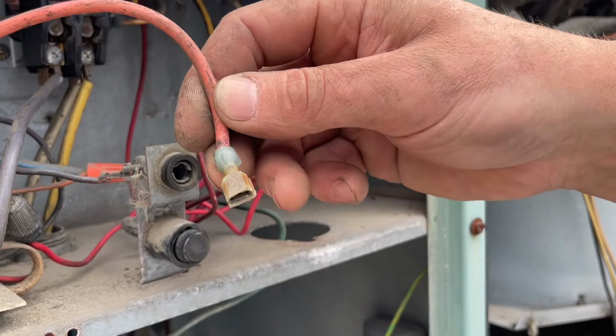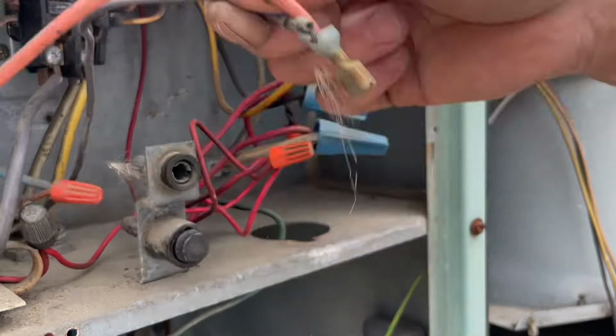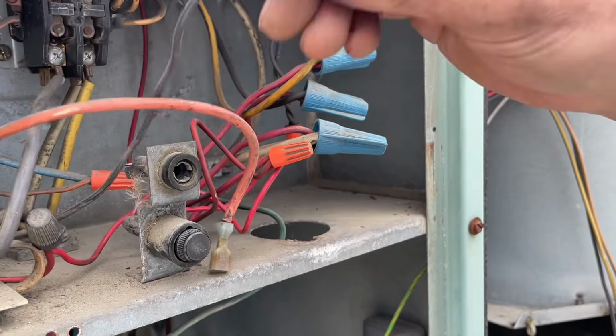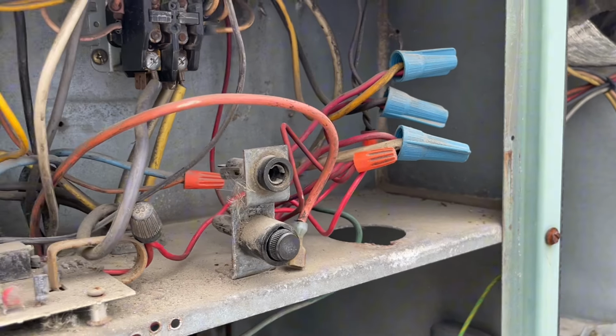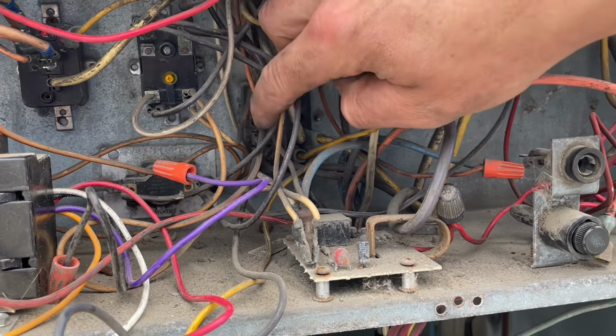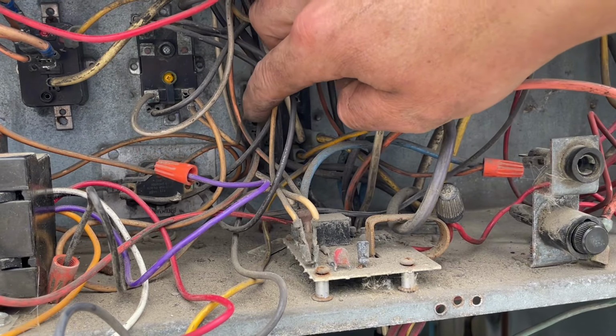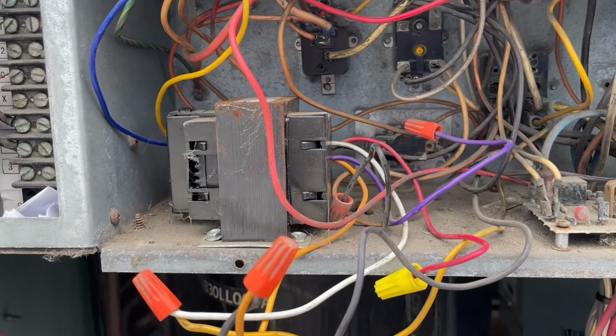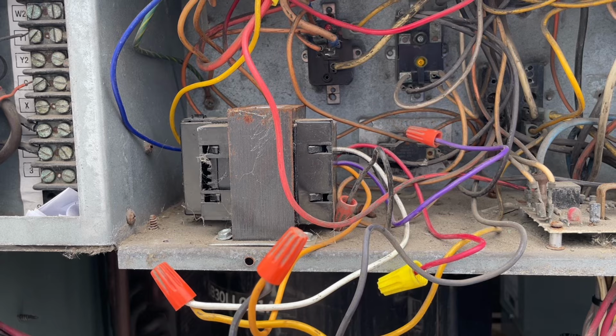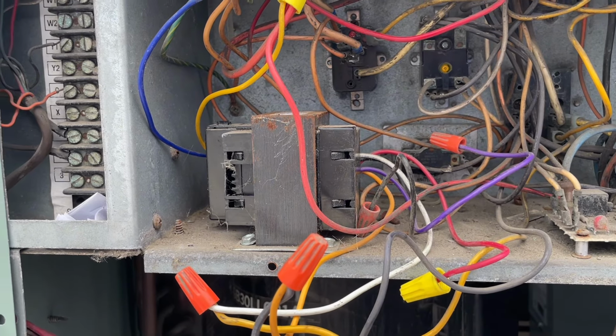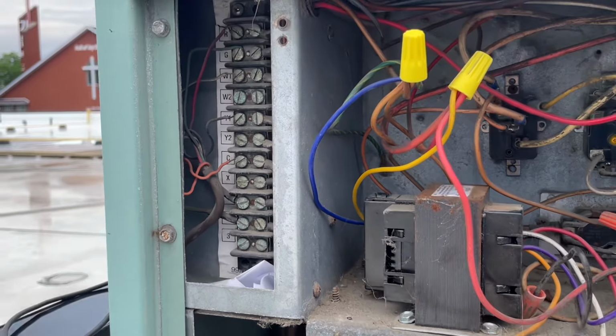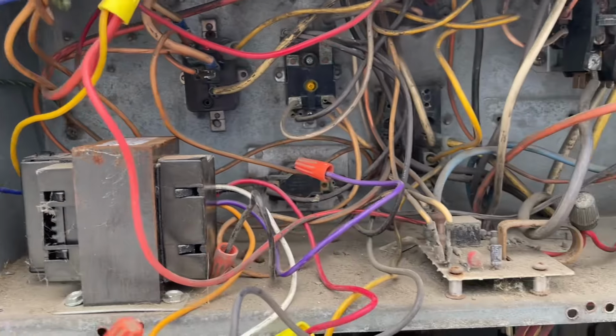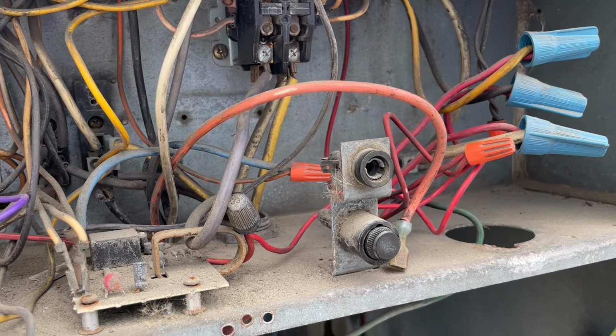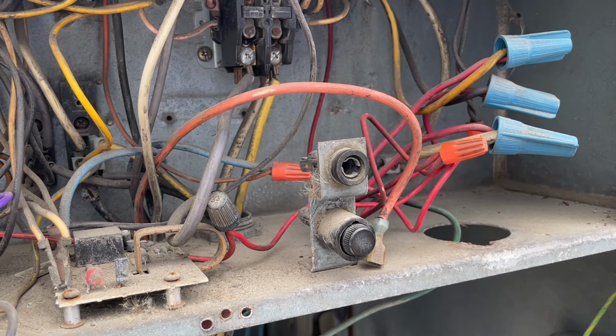That's our power from our transformer, feeding a terminal board or terminal strip back here, which in turn gives power into our 24 volt — 240 to 24 volt transformer — which powers our terminal strip. Our unit should start right up after we bypass this fuse. Let's quickly do that.